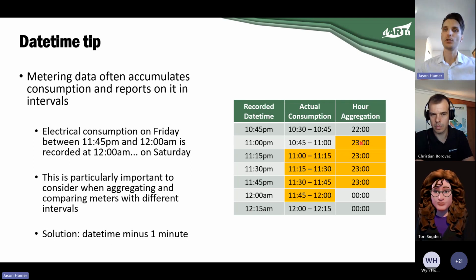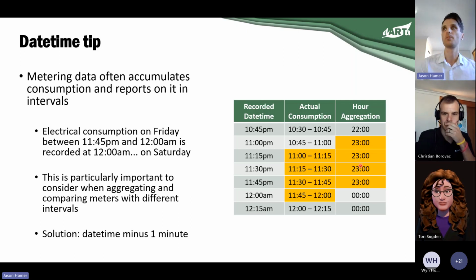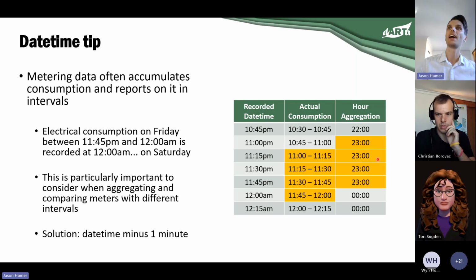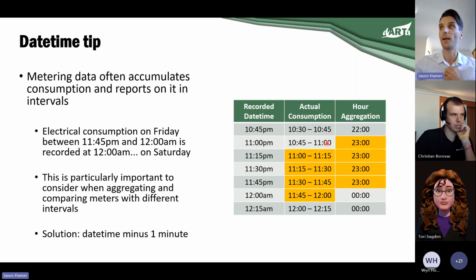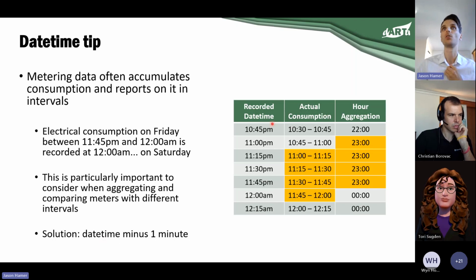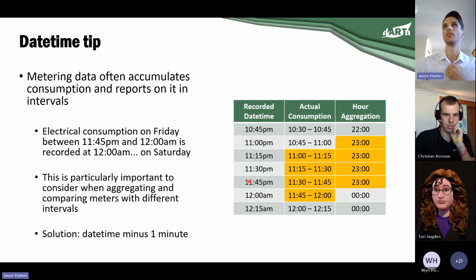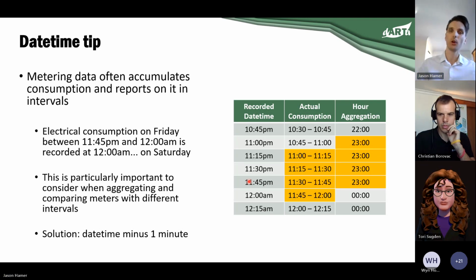This becomes a real problem when you have two different meters with different timestamps. If one meters every 5 minutes and one every half hour, the difference between them is even bigger - aggregating by 11 o'clock in the 5-minute interval, you're only missing one 5-minute increment, since it's actually grabbing the 5-minute increment from the next hour, but the half-hour increment is offset by a whole half hour. The solution is to do date-time minus 1 minute, because this forces all the recorded date-times to always be within the hour that consumption happened. Quick tip and trick.